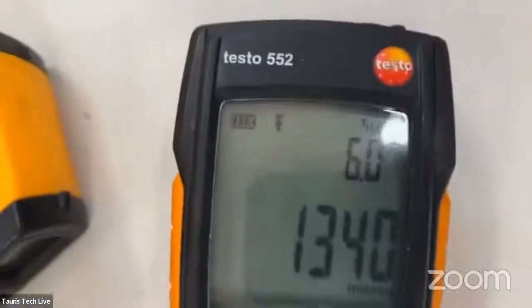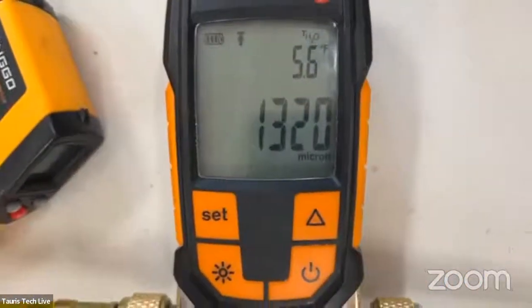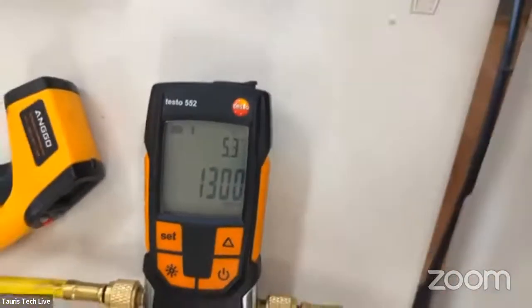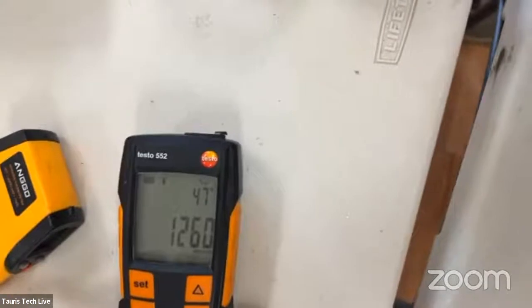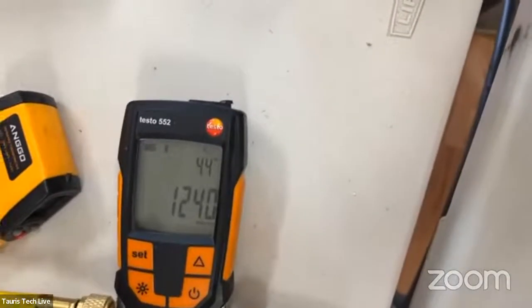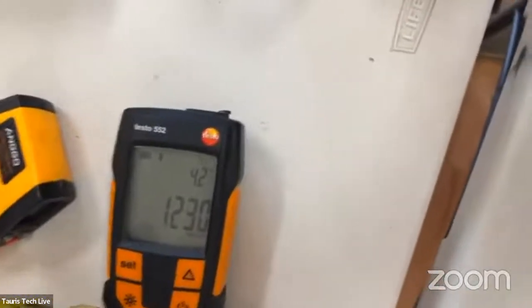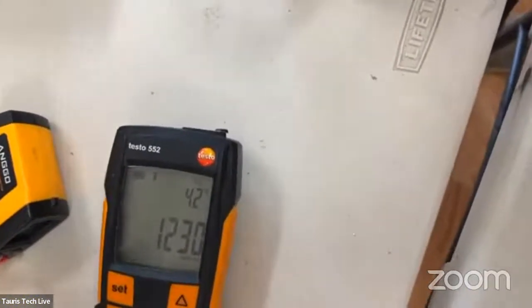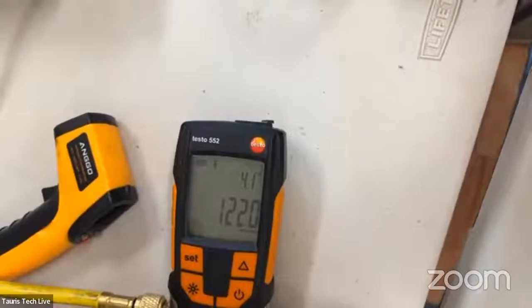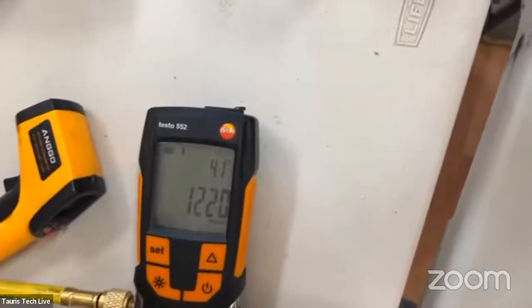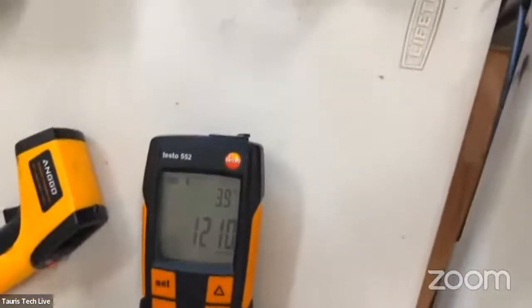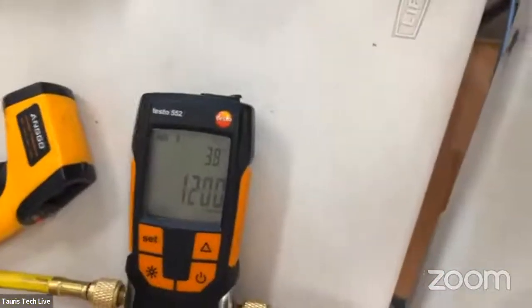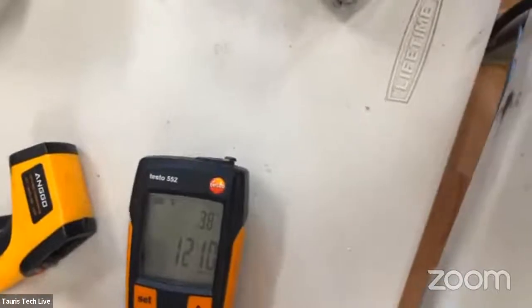Now, I'm not sure if you guys were paying attention before, but it was taking a while to get in that vacuum. Now it's actually going quicker. With the triple evacuation, I've seen jobs where, if you install heat pumps in schools, they want you to pull down to 500, then 300, then I think 200, something like that. So 500 isn't even good enough. The triple evacuation helps with that because you're flushing, then evacuating, flushing, then evacuating.